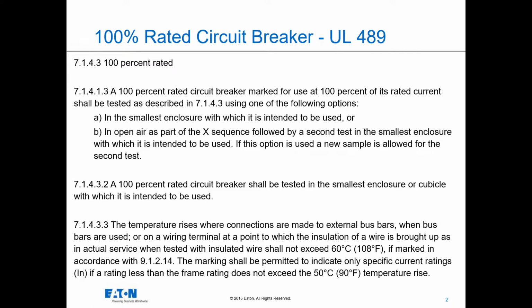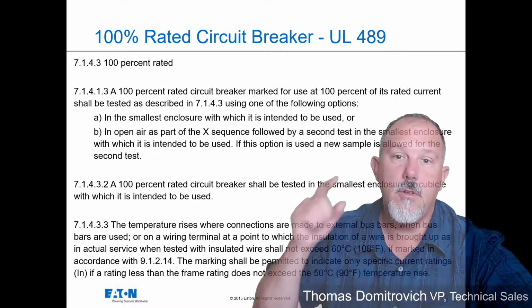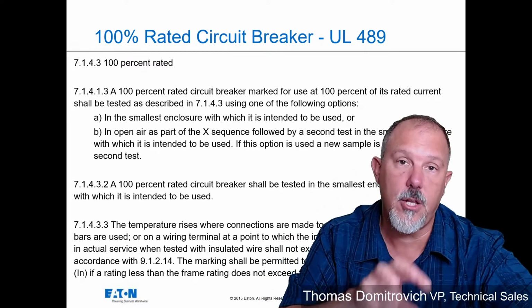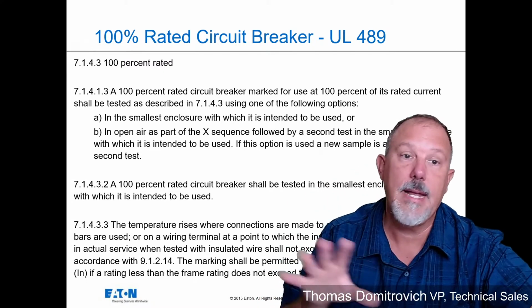So space, it's about temperature. And they say the temperature rises where connections are made to external bus bars when the bus bars are used, or on a wiring terminal at a point in which the insulation of a wire is brought up as in actual service when tested with insulated wire shall not exceed 108. So they're looking at the temperature rise on certain parts inside the enclosure and also in the enclosure itself. So they're measuring temperature inside.